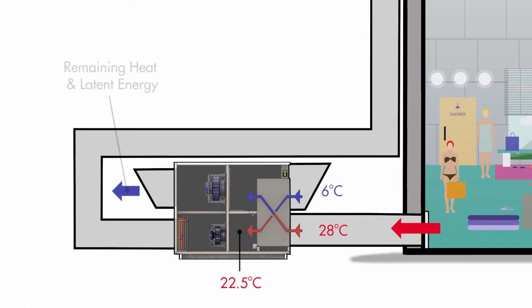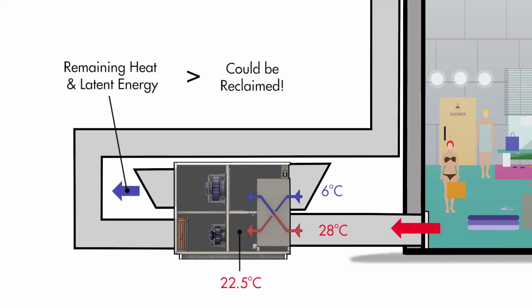This is great! But what about the remaining heat and latent energy left in the exhaust air after passing through the heat exchanger? For much of the year, this remaining energy exceeds that of the outside ambient air, making it a much more efficient heat source. This is all energy that could be reclaimed and reused to lower the energy consumption of the pool facility.